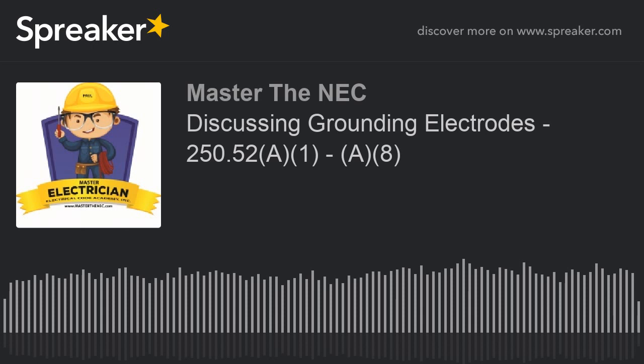Now, it says if we have two or more grounding electrodes that are bonded together, they are to be considered a single grounding electrode system. So the two rods, when they get bonded together, are part of your grounding electrode system. They work as one. Now, that's a system, but there's still one electrode that you're supplementing with another electrode. But when you tie everything together, then it all works as one system. And that's what we're trying to do, tie them all together as one.